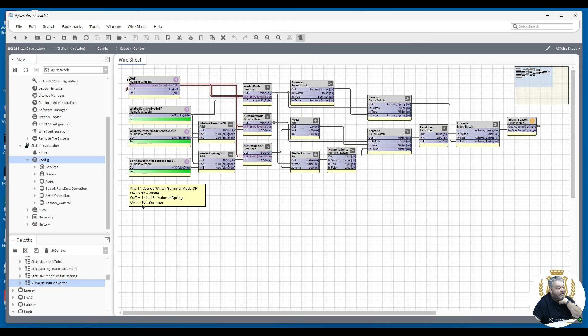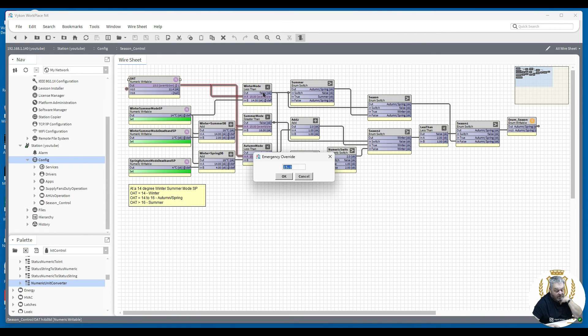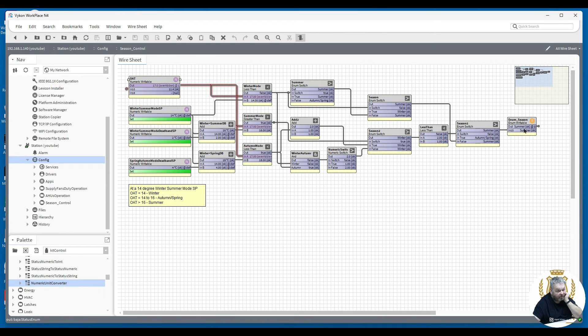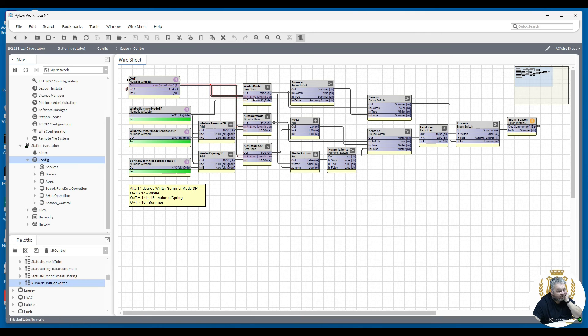Above 16 degrees is summer, so let's put that to 17 degrees — and we're in summer mode. Put that back down, and we're back into winter mode. So: winter is less than 14, outside air 14 to 16 is autumn/spring mode, and greater than 16 is summer mode. Let's put that back to 15.